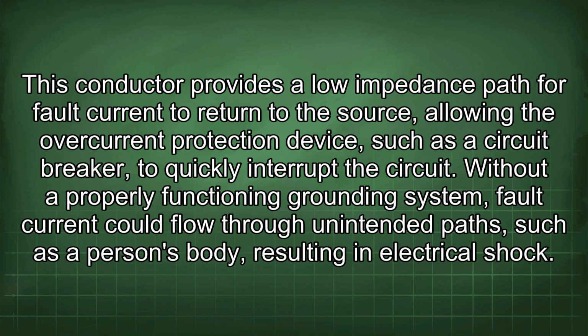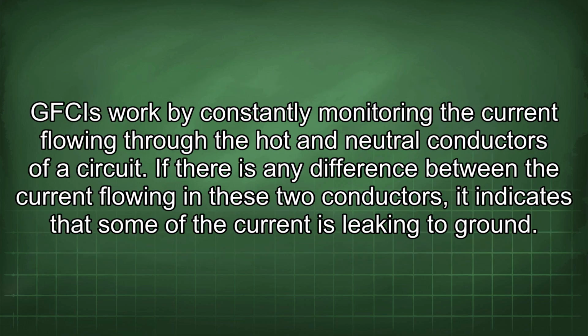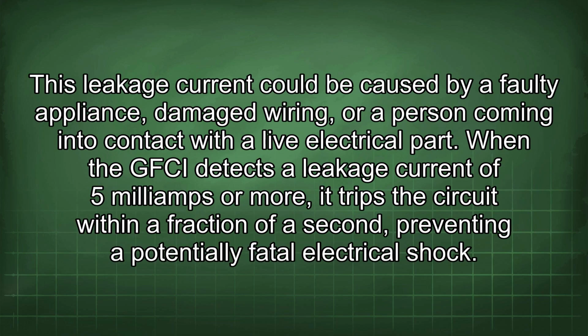Without a properly functioning grounding system, fault current could flow through unintended paths, such as a person's body, resulting in electrical shock. GFCIs work by constantly monitoring the current flowing through the hot and neutral conductors of a circuit. If there is any difference between the current flowing in these two conductors, it indicates that some of the current is leaking to ground. This leakage current could be caused by a faulty appliance, damaged wiring, or a person coming into contact with a live electrical part.